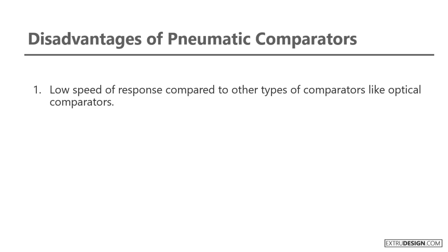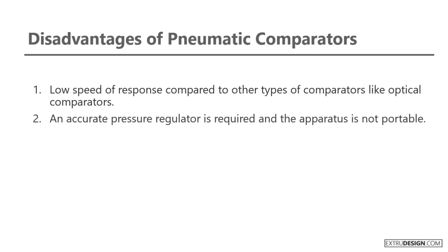Disadvantages of pneumatic comparators: low speed of response compared to other types of comparators like optical comparators; an accurate pressure regulator is required and the apparatus is not portable; and the scale is not uniform.